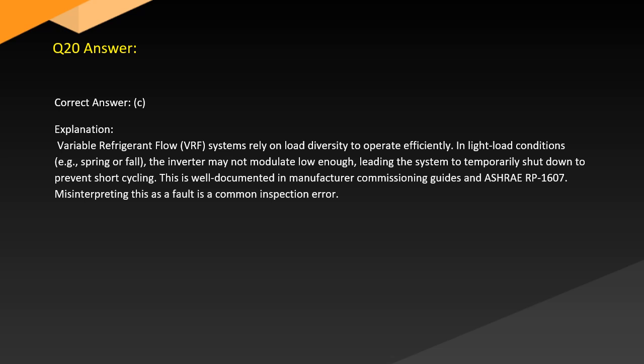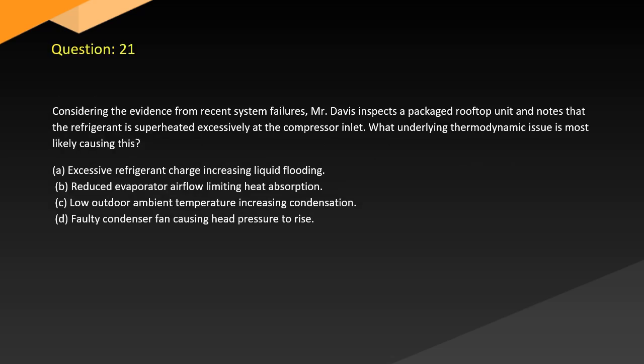Answer. Correct answer: C. Explanation. Variable refrigerant flow (VRF) systems rely on load diversity to operate efficiently in light load conditions, e.g. spring or fall. The inverter may not modulate low enough, leading the system to temporarily shut down to prevent short cycling. This is well documented in manufacturer commissioning guides, and ASHRAE RP-1607. Misinterpreting this as a fault is a common inspection error.